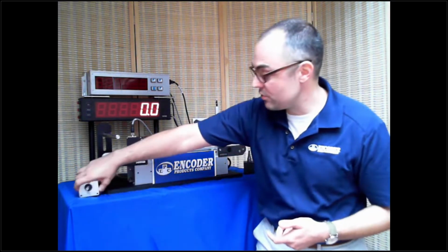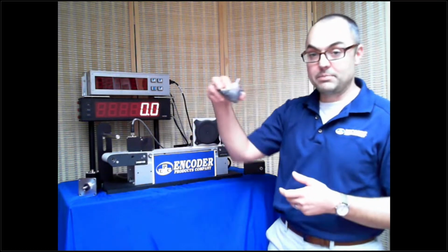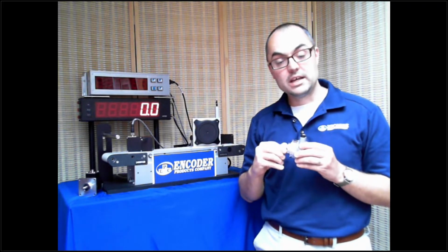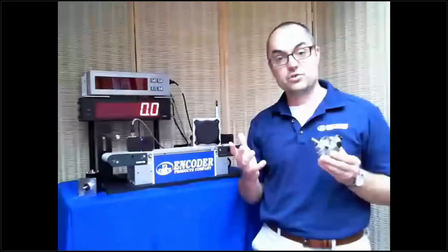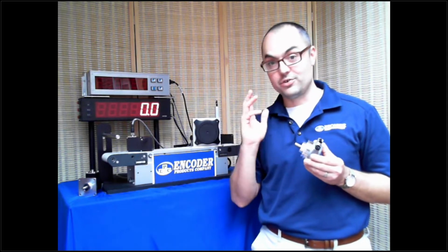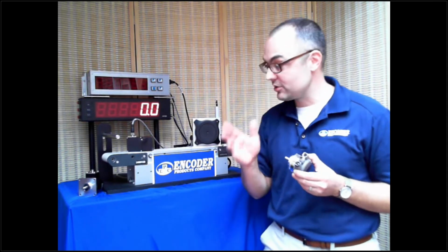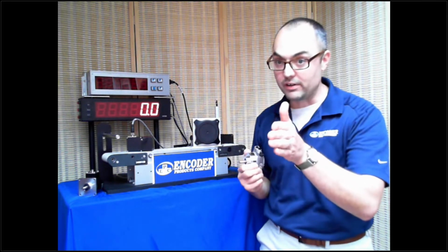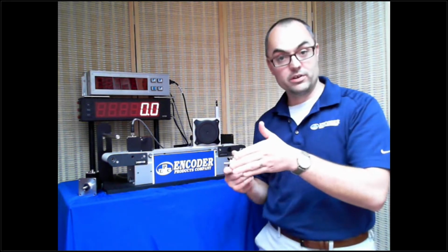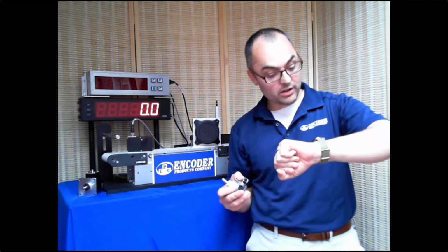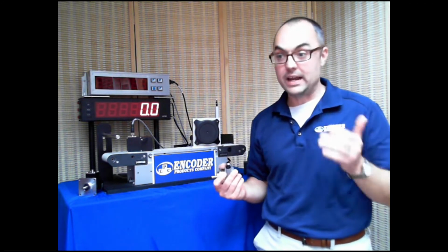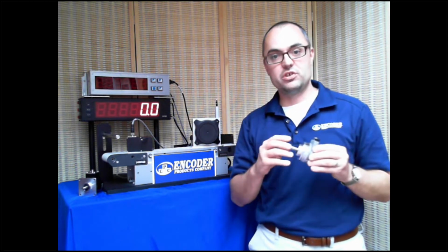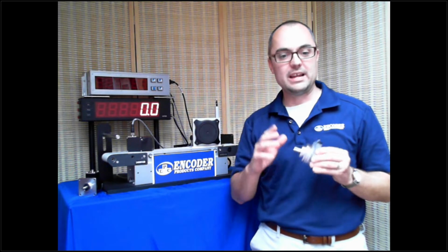Very similar to an incremental encoder is an absolute encoder, except that it actually gives you a discrete position. Whereas an incremental encoder is just going tick, tick, tick, like the second hand on your watch, in a circle, an absolute encoder is saying it's 130, it's 131, it's 132. And you can walk away and check back and look at your watch and go, oh, now it's 240. I didn't have to actually count the pulses in between. Absolute encoders give discrete positions within a circle, constantly reporting that, not just ticks.